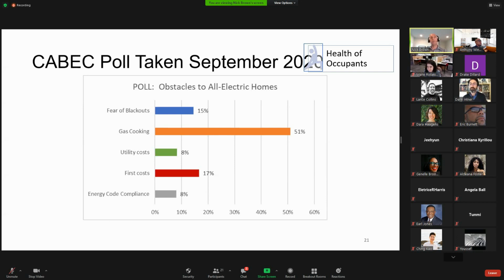An electric tankless water heater - they make them, and they're popular in Florida and Arizona, but they never beat 100% efficient. Same with an electric tank. So if you're going to go electric, a heat pump water heater has to be the way. Electric resistance is a no-no today when we have such a superior technology in heat pumps. They are out there, but you'll have real trouble complying with Title 24 with electric resistance water heating.